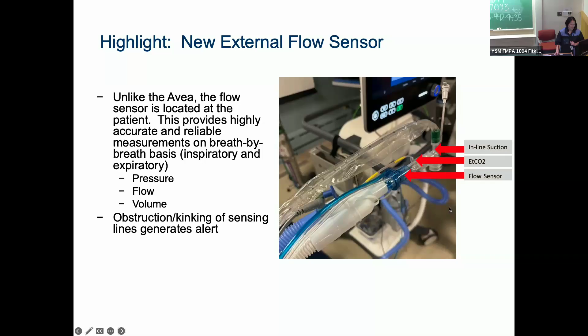The downside to this, so here you see the sensor, and it's blue, and it's next to where the patient is. The downside to this, say this is the patient, is that this ventilator, I had a hard time drawing. No, it's a little ghastly. This flow sensor has to be kind of vertical. It has to be at least upright and vertical. It is sensitive to condensation, so it tends to build condensation. Certainly secretions can still reflux into the sensor and clog it if it's hanging down.